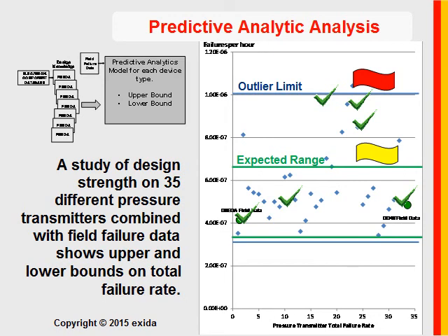Thank you so much. If failure rates from the component database that exida uses in their FMEDAs are validated with field data, why do we want operators to collect failure data? That's a good question. I would believe that properly collected field data is stronger than generic failure data. I would believe that properly collected field data will give you a failure rate lower than generic failure data, at least the generic failure data from FMEDA. However, I'm not familiar with FMEDA component databases, so I cannot really comment.